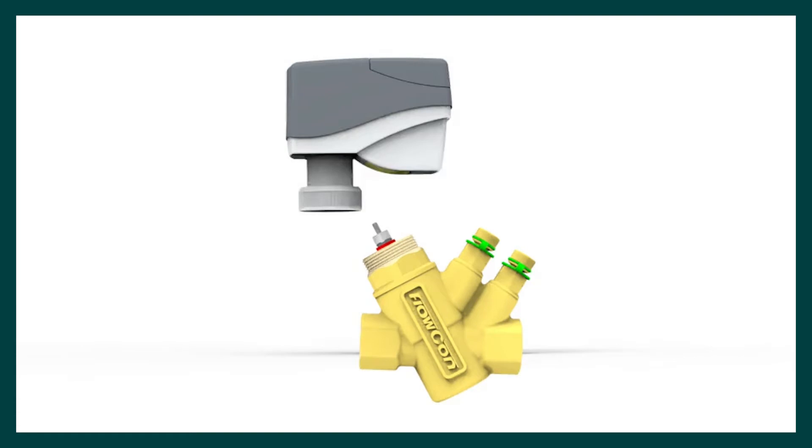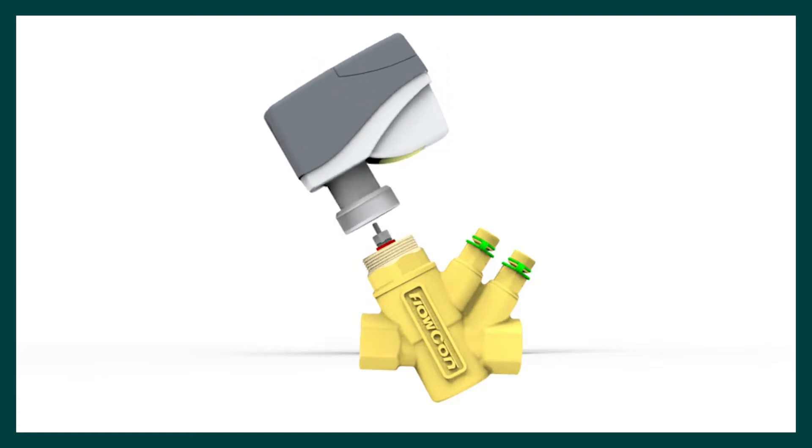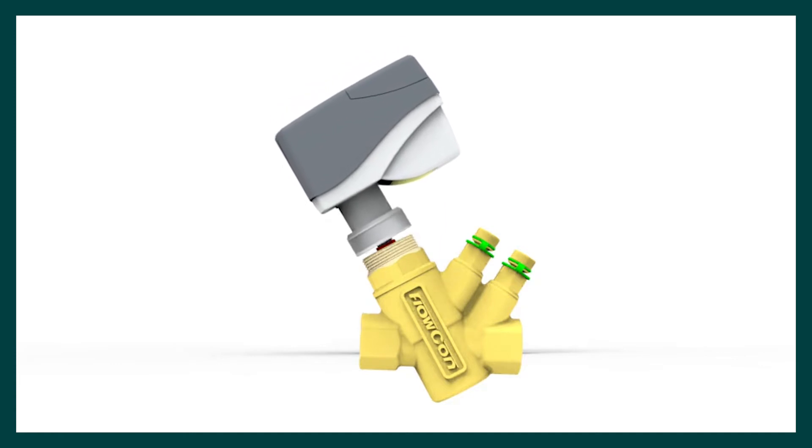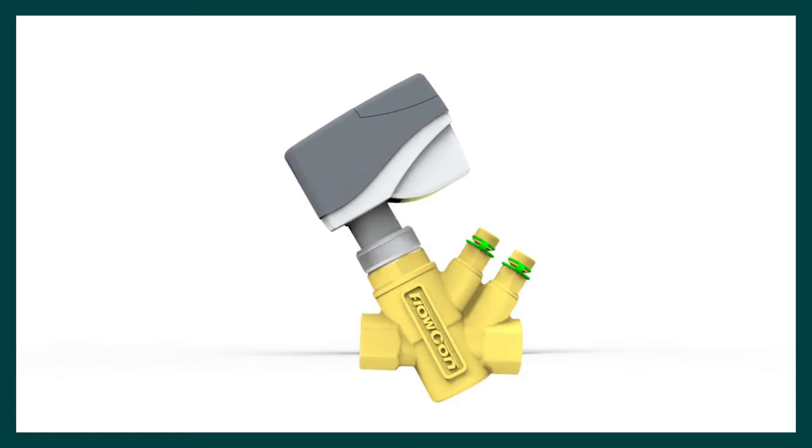Align the actuator to the PICV threaded insert. Rotate the locking ring clockwise by hand until hand tight. The actuator is suitable for mounting upside down, but we recommend mounting the actuator above the horizontal body facing upwards.